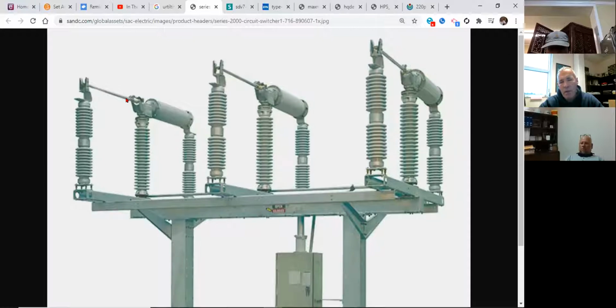As far as this switch is concerned, can it be open and these bars be closed? Yeah, yes. Okay, the opening happens in here every single time, even if you trip this open manually, or want to open it yourself, or SCADA it to open itself, that's going to happen in this area. Then a motor is going to turn, you see the bar that connects all three together, these insulators are going to rotate and the bar is going to swing up. That's going to make your visual open point, right? But you can have an open in the tube right here and the bar still be closed. So don't trust what you see here.